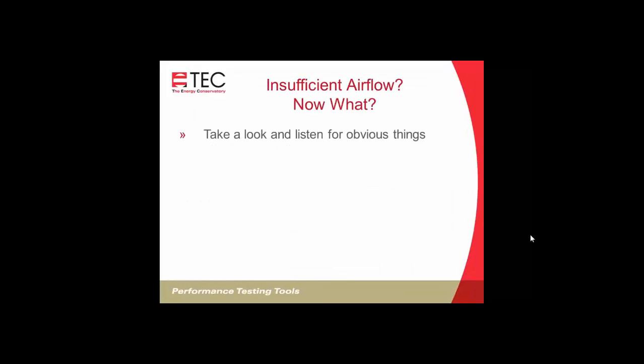So now we've covered methods of measuring your air handler flow accurately. And what if your numbers come up to be insufficient? You don't have enough airflow, total airflow going through your system. So what are some options? How do you figure out what the issues might be that need correction? To start out with, we'll just take a look and listen for some obvious things.